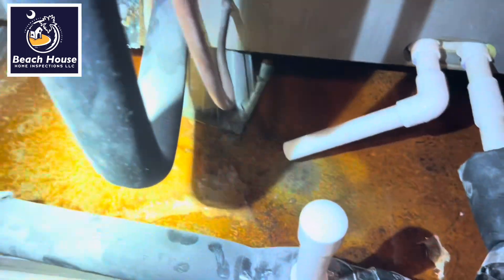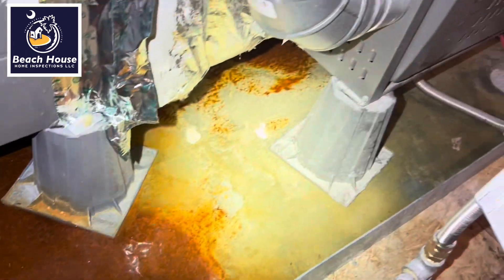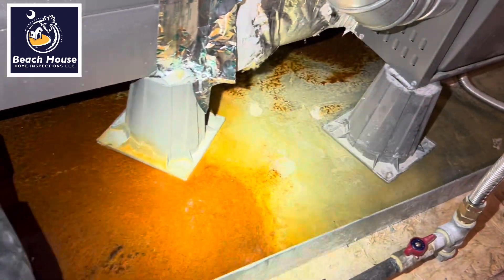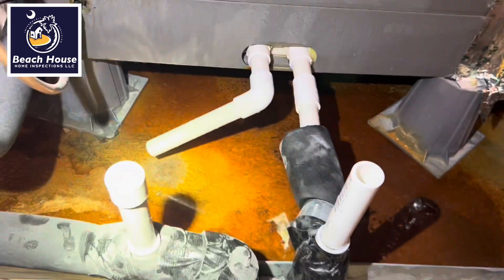The water's going into the pan. Look at all this damage that defect has created. They're going to have to get this pan replaced — this will eventually go right through the pan into the ceiling below.